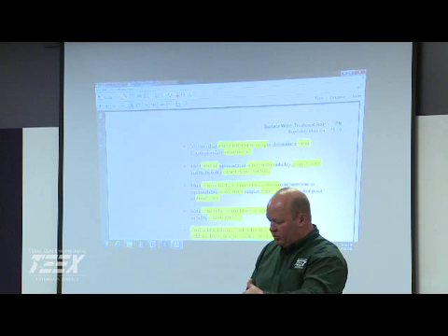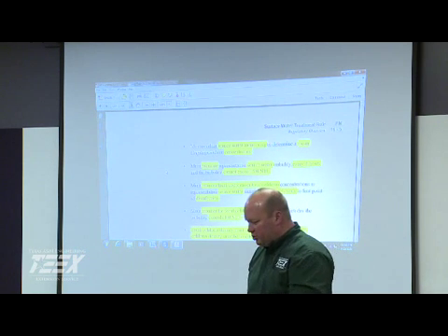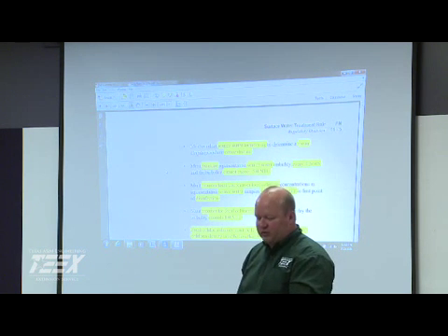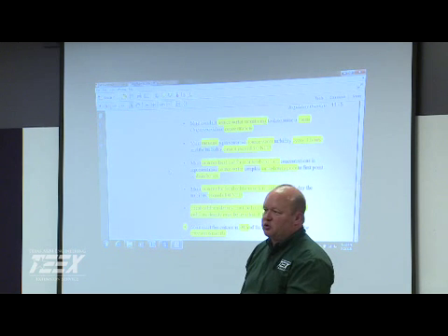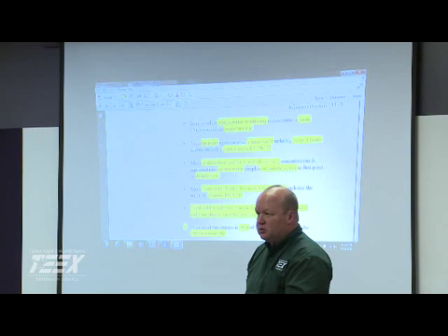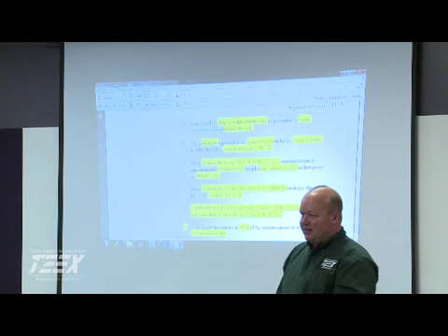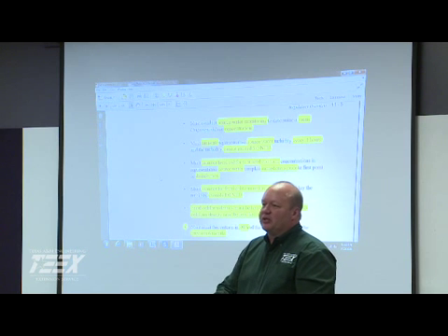But if you're on an unfiltered surface water source, then you have certain parameters. You have to measure your source water every 4 hours. It can't exceed 5 NTUs. Really, I doubt that there's anybody doing that. Almost everybody off the surface is treating. Yeah, that's one of the requirements. I want to say there's maybe one, and it may be up in Johnson City, I think, but I'm not 100% sure. So I'll highlight this for them.